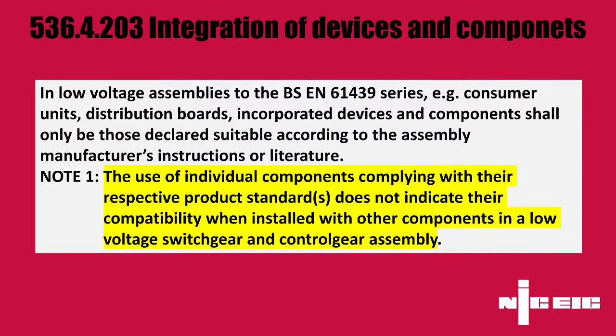We've got to almost think of it in two ways. Yes, I've selected the right product, but now I want that product to work with other products in that consumer unit assembly, and the manufacturer of that assembly will guarantee its characteristics so long as we stick with their rules, and their rules will be that you use their components in association with their manufacturer's instructions. And it's understandable, because they will have done something often referred to as type testing. They'll test all of that assembly as a whole with all of its different variations, just with their manufacturer's equipment, to make sure, as you say, that there are no heat issues, no electromagnetic interference, and no possible inductance issues of one thing inducing voltages and currents in other parts of the assembly.